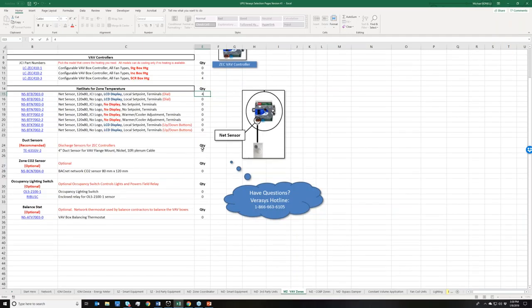The discharge air sensors aren't required for our Verasys controllers, but again, as I said before, these sensors don't cost a whole lot. Personally, I like to know when my VAV box is heating, and specifically when it's not heating, and I can do that using these discharge air sensors. So they're just a no-brainer—add them in there. Where it's going to be costly is coming to do the install, and it's not going to be a whole lot. I'm going to stop there.